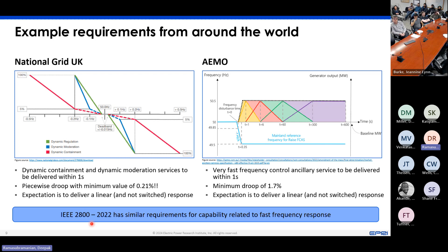Coincidentally, IEEE 2800-2022, a standard for performance requirements for inverter-based resources, also has similar requirements for capability related to fast frequency response. Now, the mere presence of a capability doesn't necessarily mean it will be utilized, but we'll now see what happens if you actually utilize some of this capability. So let's take a look at voltage control.